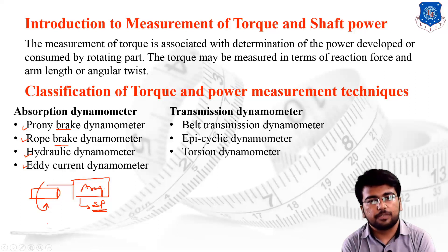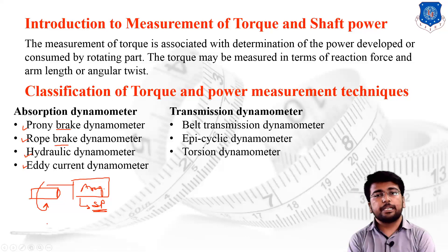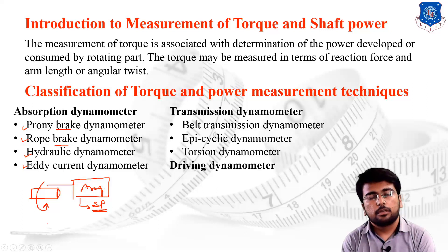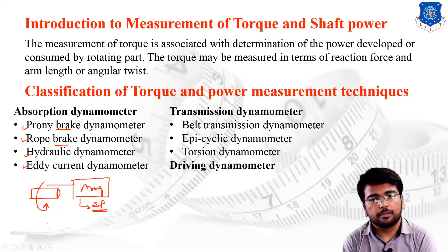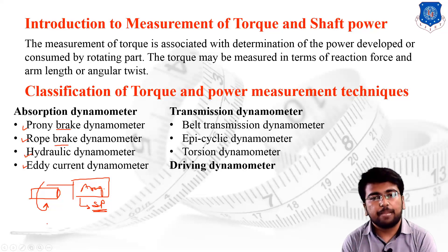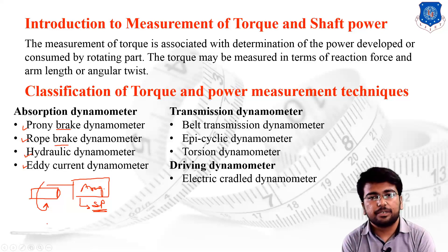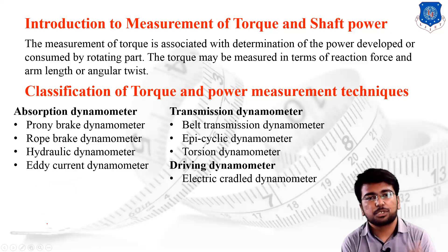The third category is the torsion type dynamometer, in which motion is transferred as an angle of twist from one shaft to another, and the angle of twist is measured to determine shaft power. The fourth and last category is the driving type dynamometer, whose primary application is the electric cradle dynamometer — an instrument based on electric circuitry and sensors for measuring shaft power.